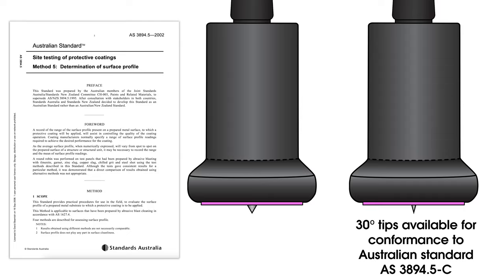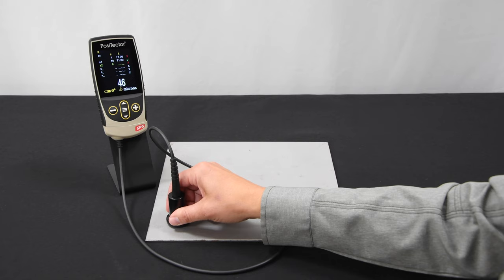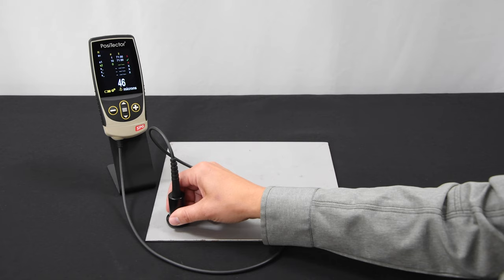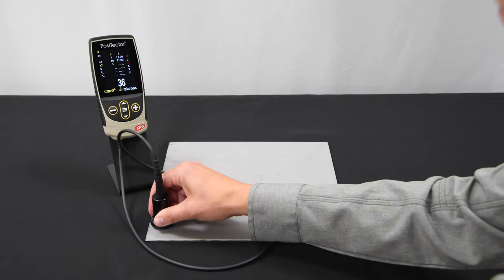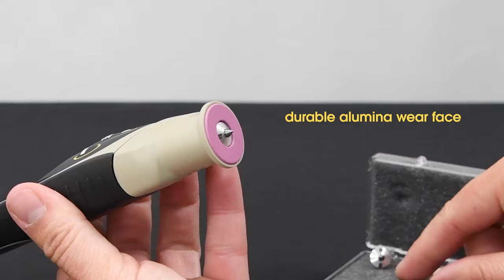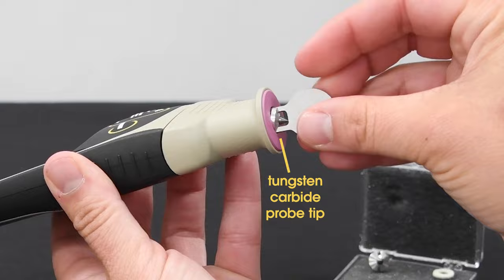Models with a 30-degree probe tip are available for compliance with Australian standards. A fast measurement rate of over 50 readings per minute makes it ideal for quickly measuring surface profile over large areas. All probes feature a durable alumina-wear face and field-replaceable tungsten carbide probe tips for long life and continuous accuracy.